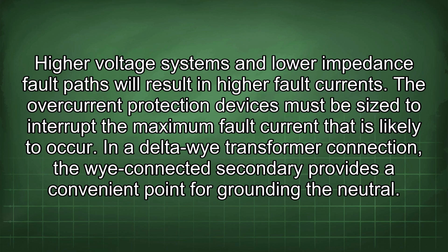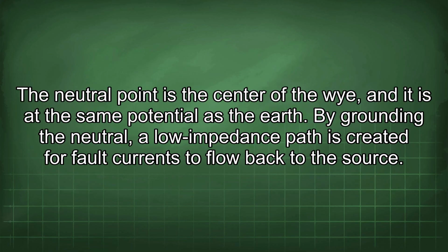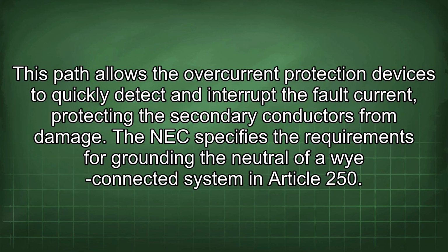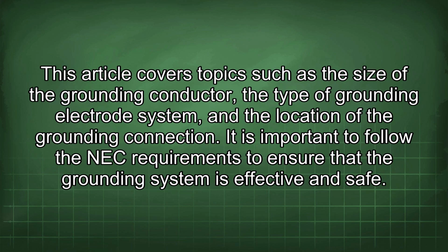In a Delta-Wye transformer connection, the Y-connected secondary provides a convenient point for grounding the neutral. The neutral point is the center of the Y, and it is at the same potential as the earth. By grounding the neutral, a low impedance path is created for fault currents to flow back to the source. This path allows the overcurrent protection devices to quickly detect and interrupt the fault current, protecting the secondary conductors from damage. The NEC specifies the requirements for grounding the neutral of a Y-connected system in Article 250. This article covers topics such as the size of the grounding conductor, the type of grounding electrode system, and the location of the grounding connection. It is important to follow the NEC requirements to ensure that the grounding system is effective and safe.